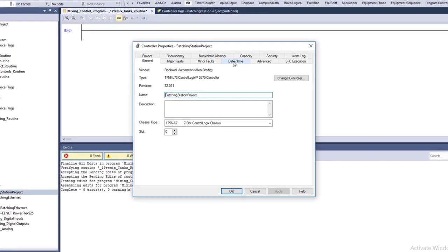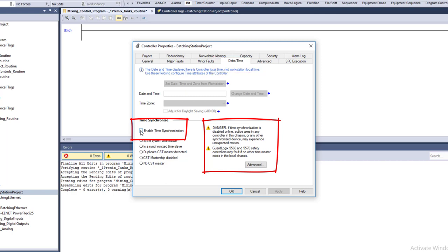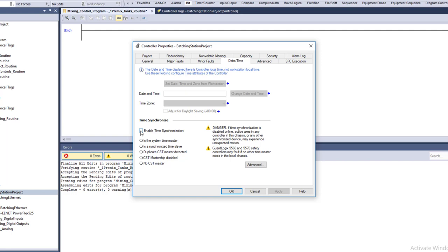So, this is date and time, and this is what you're supposed to enable on any kind of system that uses a servo system, right? So, unless this is a system that is, say, for instance, a processor that is being controlled from basically acting as a slave or a secondary, then it would not be time synchronization. But, if it is the only processor that's controlling the servos that is in its servo group, then time synchronization needs to be checked. This little checkbox, under date and time, this little checkbox right here.